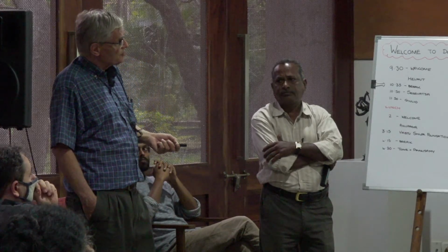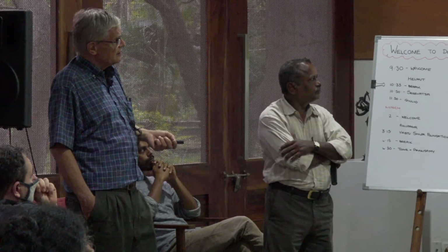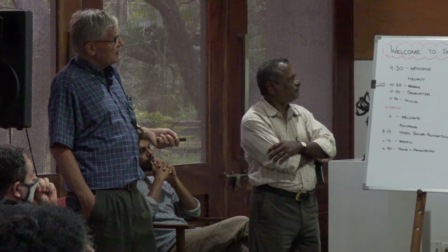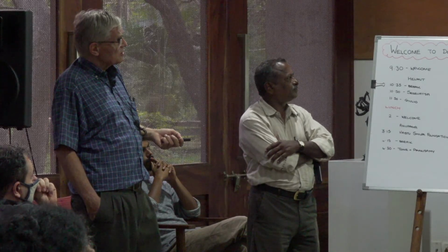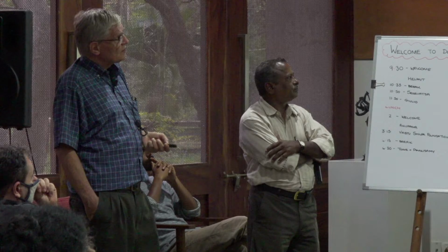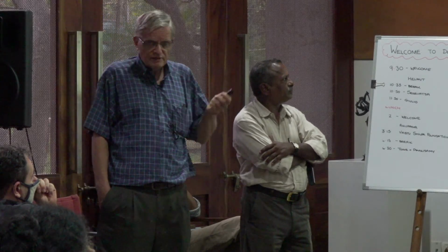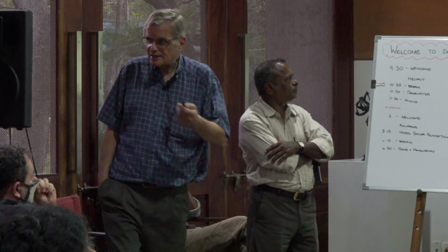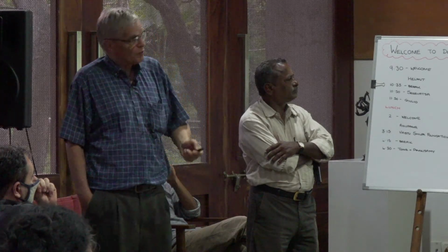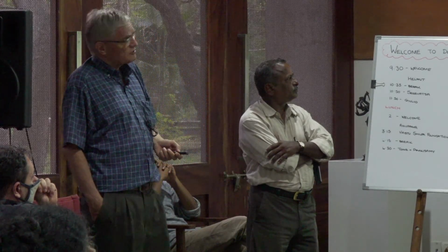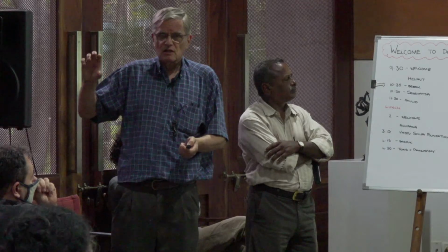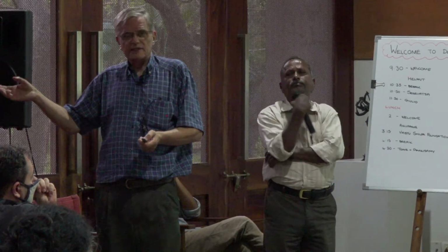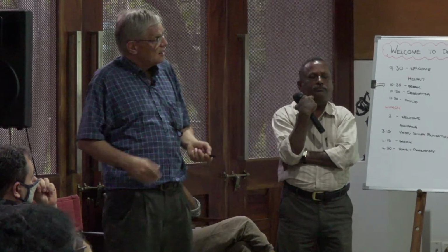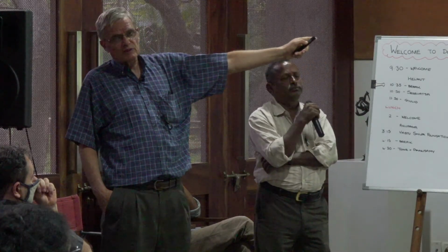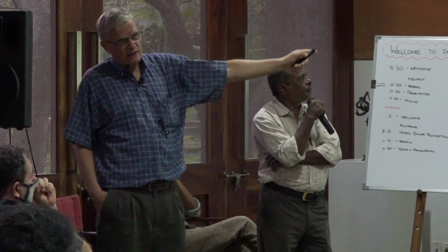So we looked at various options. I won't bother you with the details, let me go straight to the conclusion. This was plan 1: we keep the 22 kV from TNB until they change, and we step it down ourselves. Option 2 was dual ratio transformers, so they can be switched over from 22 to 11 once the 11 comes. We initially did this option; the first 4 or 5 transformers are like this.